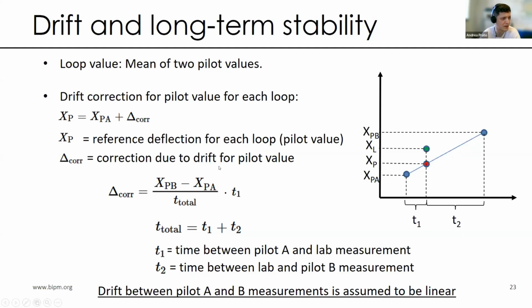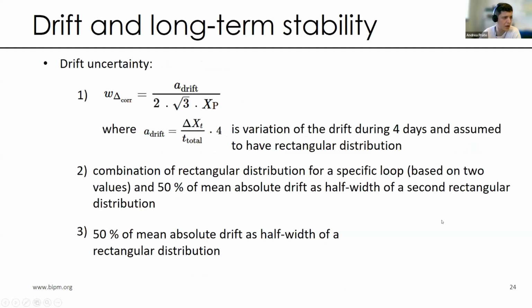So by using this formula, basically a linear fit is performed between the two pilot measurements, and through a linear regression, we can calculate the pilot value for each loop, and this can be compared to the deflection measured by the participant laboratory. Okay, how can we consider the uncertainty of this drift?